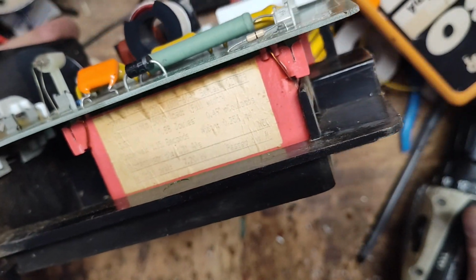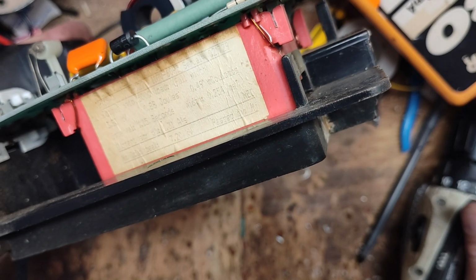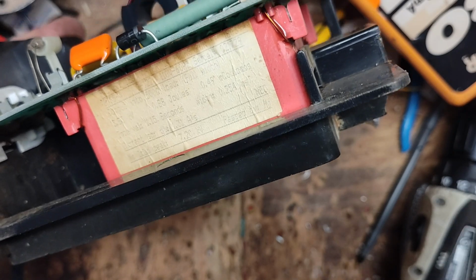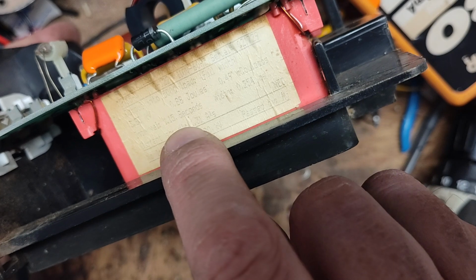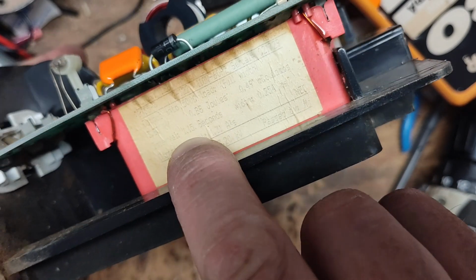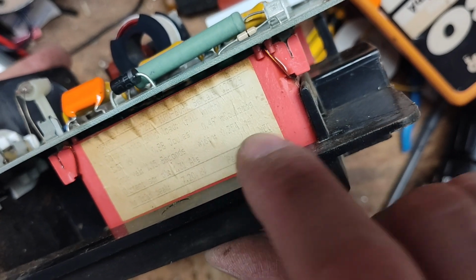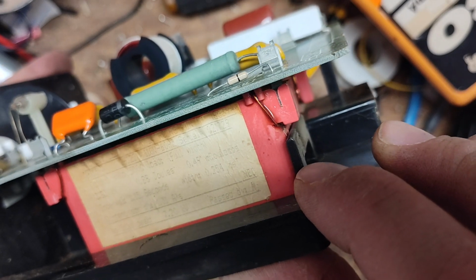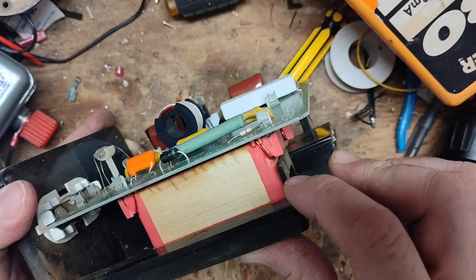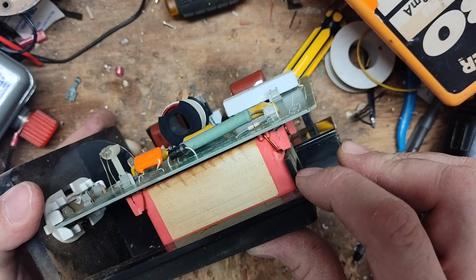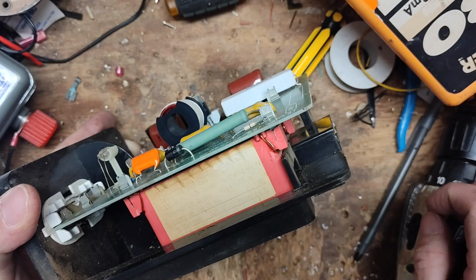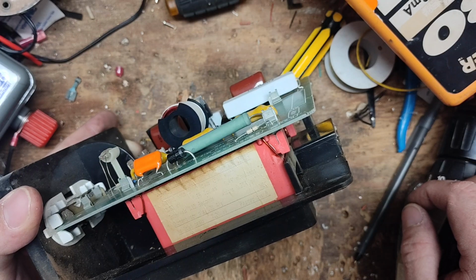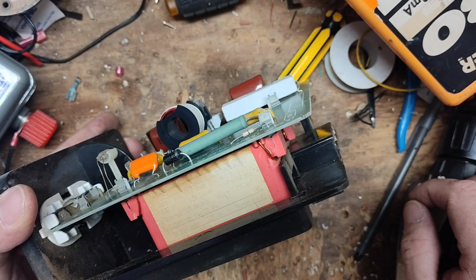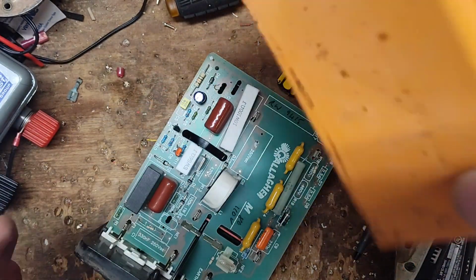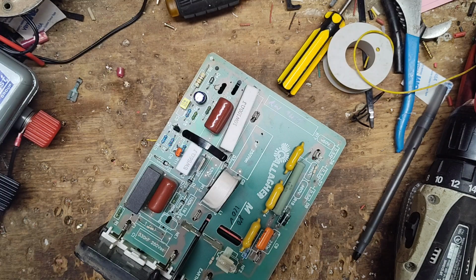You can hardly read it. Let's see. They've got some of the specs. 1.15 seconds. They do have the pulse interval. Pulse interval is 1.15 seconds. Can't hardly read it. And the pulse width was 0.25 or... I can't read it. Oh, whatever. And then the peak volts was 7.2, and we were reading 6.9, so right in the same ballpark. And then stored joules was 0.8, this is a 0.88 stored joules, and what we were reading was output joules because we were testing at the output terminals. We weren't testing the capacitor inside there.